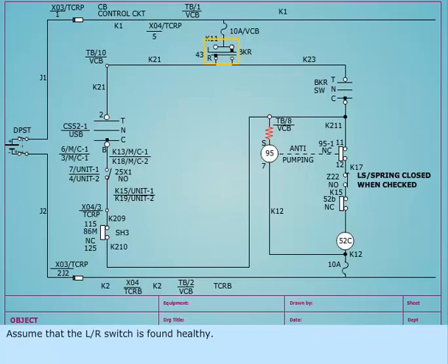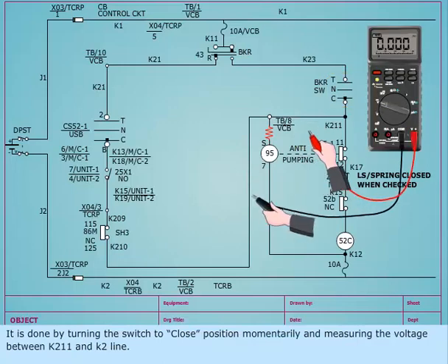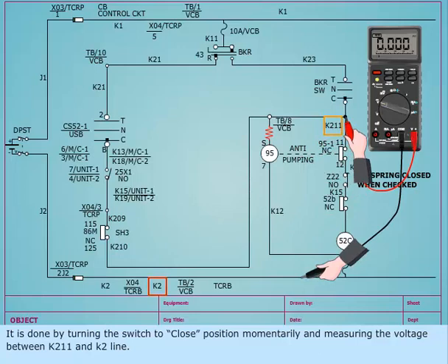Assume that the L/R switch is found healthy. Next, the TNC switch should be checked for healthiness. It is done by turning the switch to close position momentarily and measuring the voltage between K211 and K2 line.